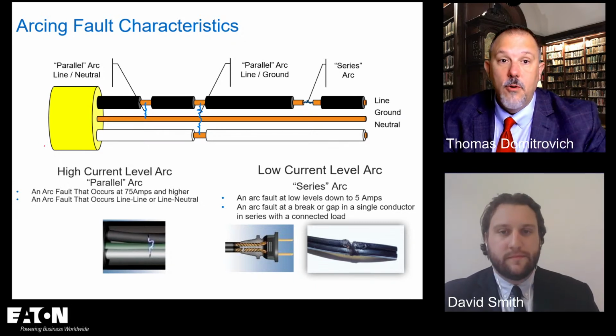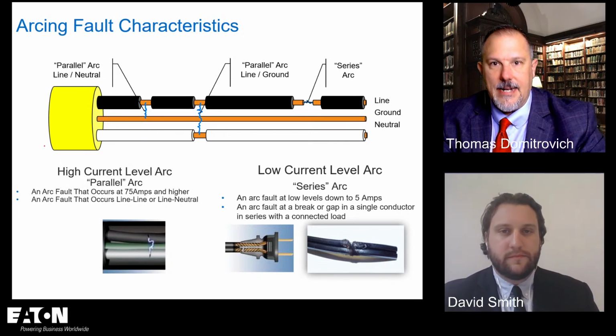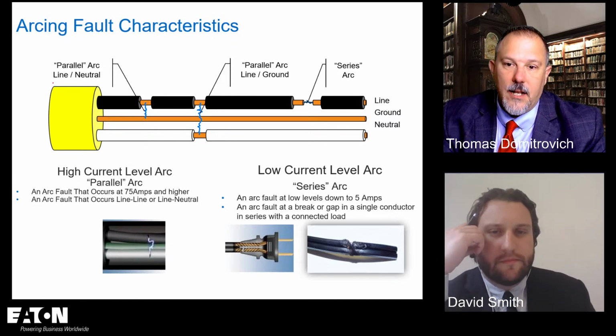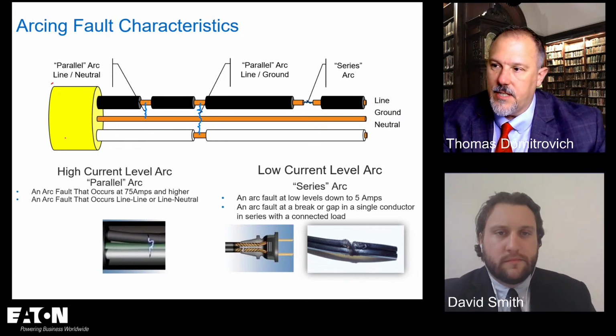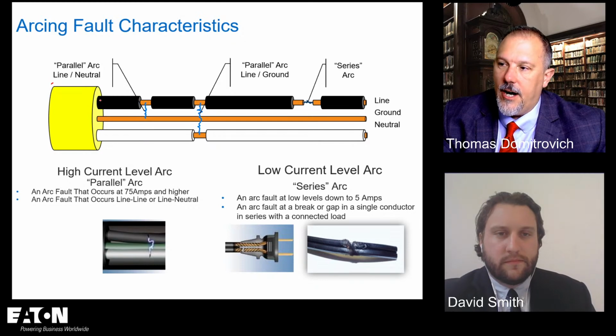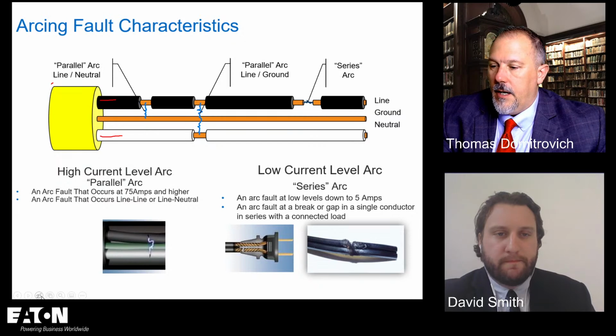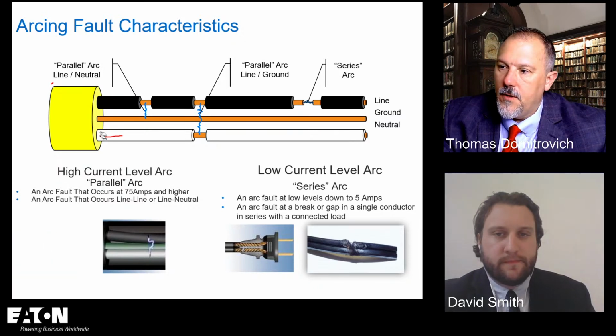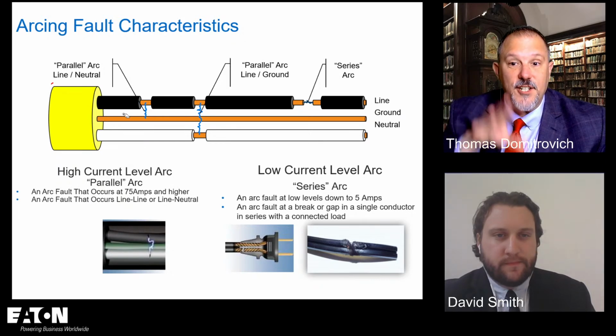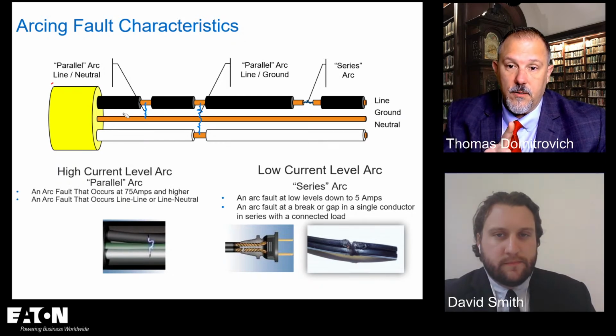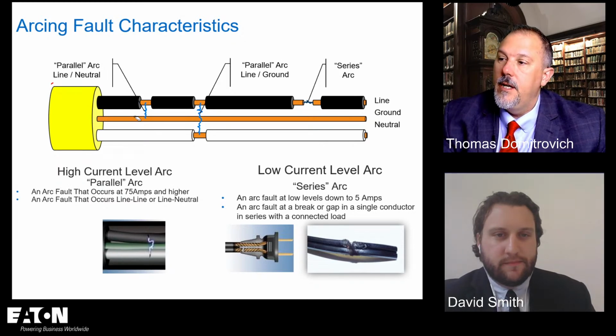If you look at UL 1699, this yellow is your NM wire. That's your typical house wire installed in residential dwelling units, where you have a hot conductor and a neutral conductor separated by a bare copper conductor, and there's usually a little piece of paper in there. The 1699 test for a branch feeder, before the combination type, tested this conductor for a fault for arcing line to line.